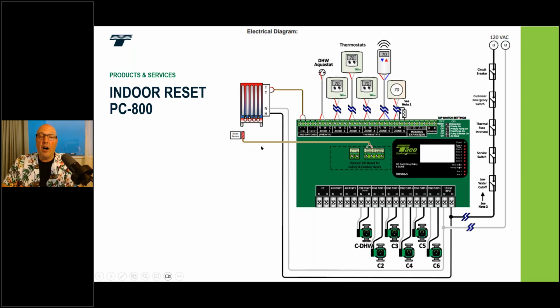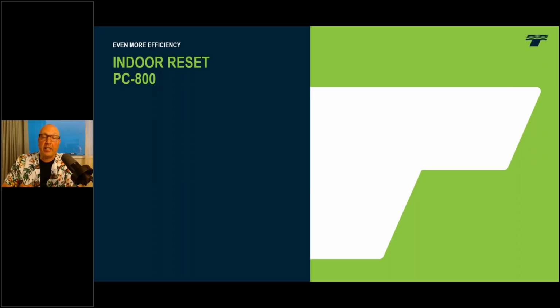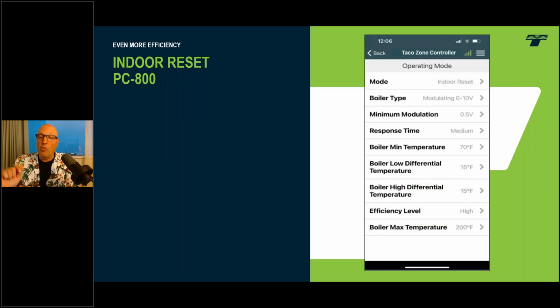All right. But what I wanted to show you were the settings on the app here. You want to take a look on how many settings this thing has. It's going to depend upon what manufacturer you've got. So if you are doing that 0 to 10 communication terminal, you choose that boiler type in here that it can do it, whether it's an on-off or 0 to 10 or 4 to 20. Then you also have to know from the manufacturer, what is the minimum modulation? How low can it go firing wise? Some of them will not go below, say, a 10 or a 20% firing rate. So you have to make sure you choose that.